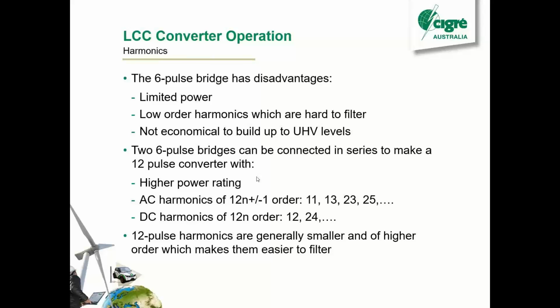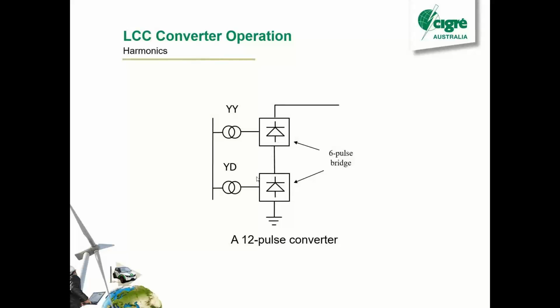So those 12-pulse harmonics, they're generally lower magnitude and a higher order, and it makes them much, much easier to filter than what you'd get with a 6-pulse converter. So this is how you do it.